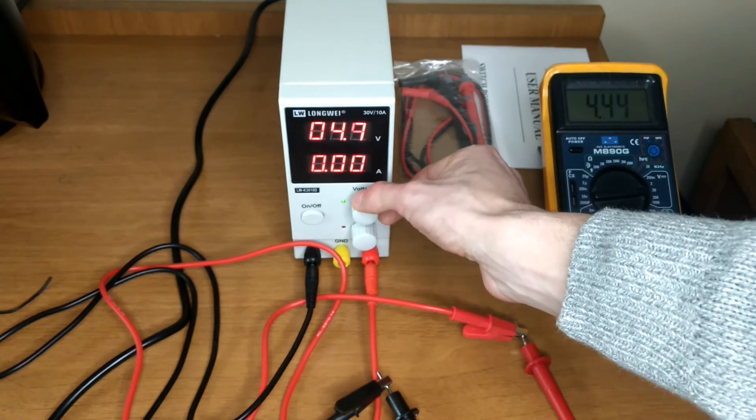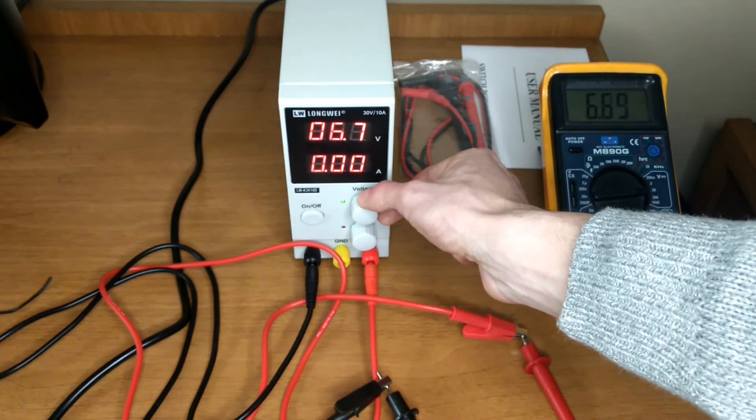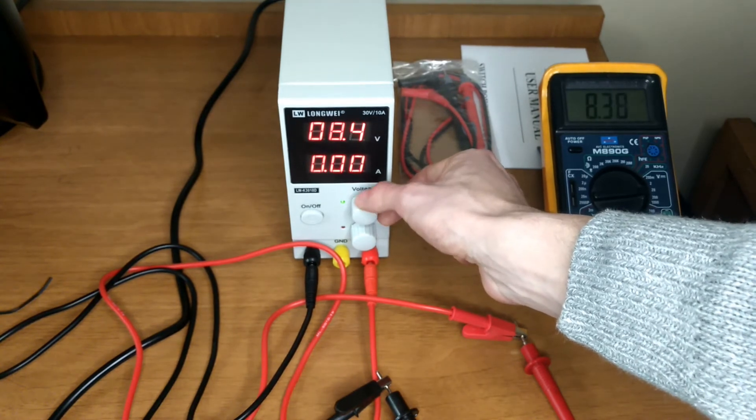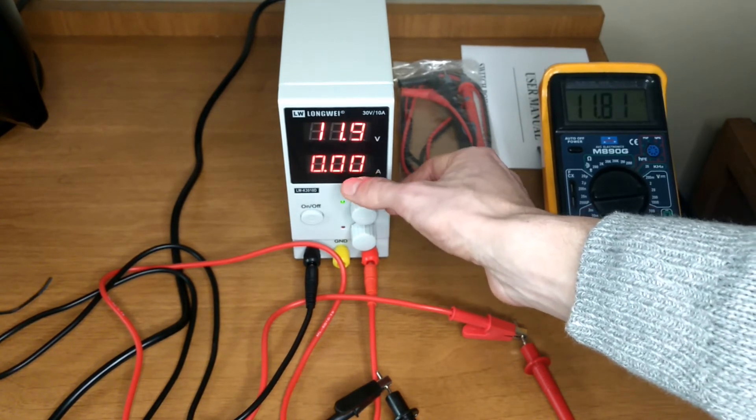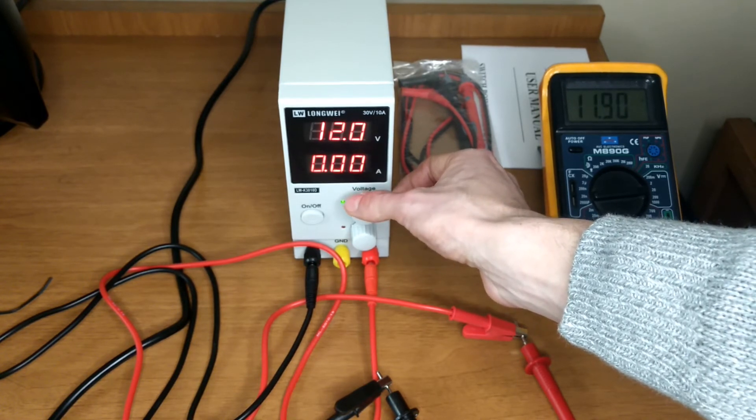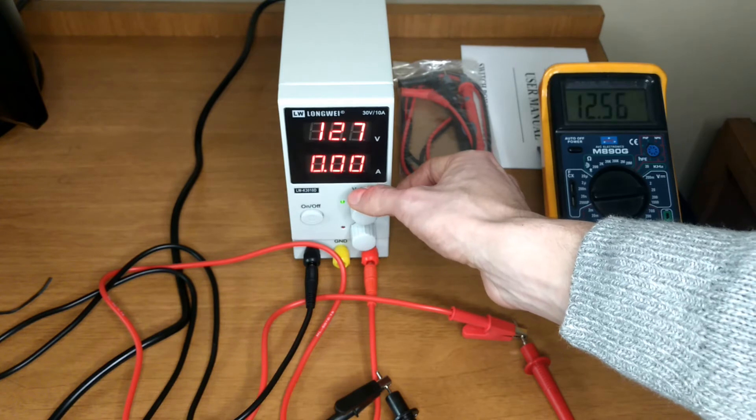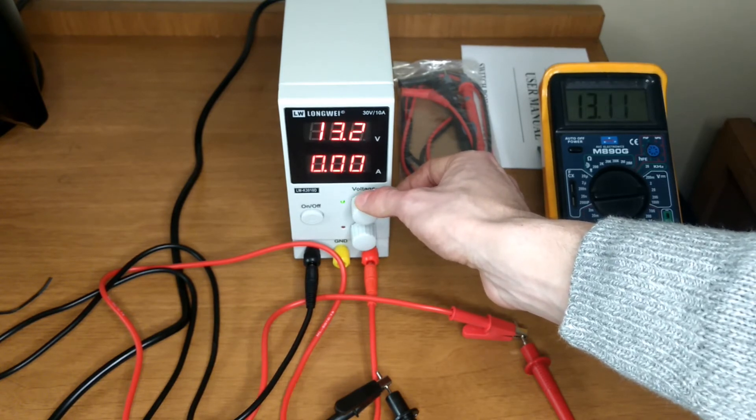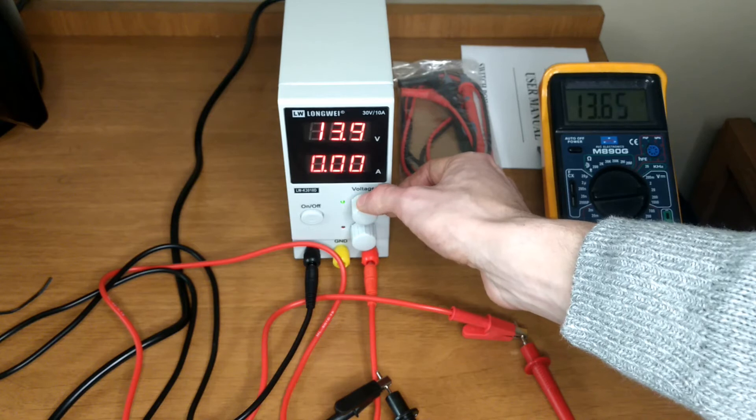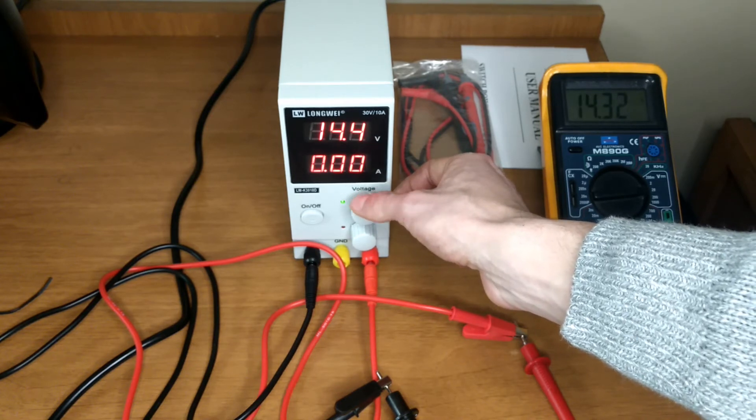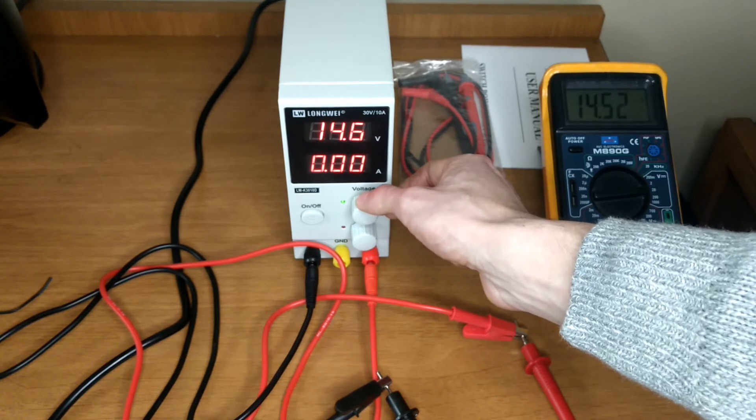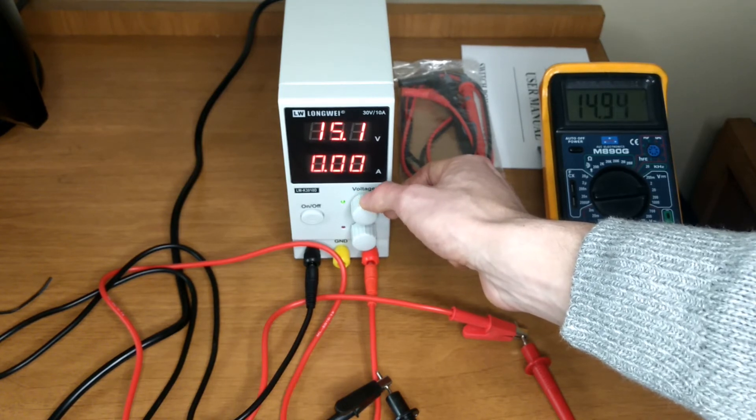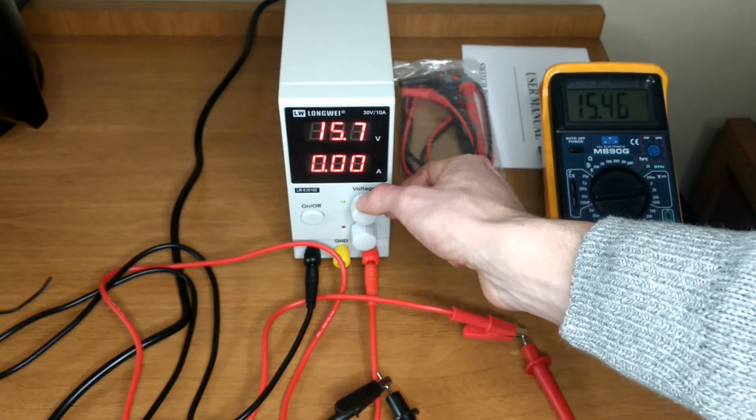Yeah, so I'll crank it up and check a couple of higher voltages. Right there at 12 volts we read 11.9 on our meter. That's like 0.8% error. I'll slowly go to the top of the range so you can see the difference we get on the display and on the meter at several voltages.